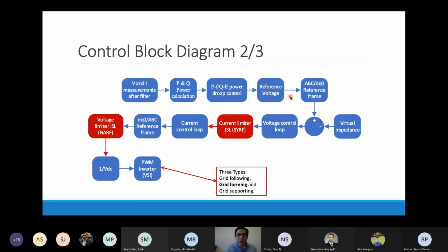After this, we go through a transformation from ABC to DQ0 reference frame, which is the common reference utilized for controlling microgrids due to its simplicity of converting a three-phase signal into a simpler DQ coordinate. So from here, we create the reference voltage. This reference voltage is fed into a voltage control loop, which includes a PI controller, basically a PID, but we are utilizing only a PI in order to set the reference current.